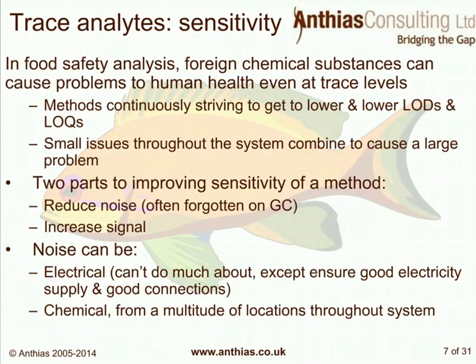Moving on to trace analysis — here we're thinking about the sensitivity of our instrument and trying to improve it to achieve lower limits of detection. In food safety analysis, foreign chemical substances can cause problems to human health even at very low concentrations. Methods are continuously striving for lower limits of detection and quantitation. Multiple small sensitivity losses through the system can combine to produce a large overall drop — so we need to consider every small problem that can occur.